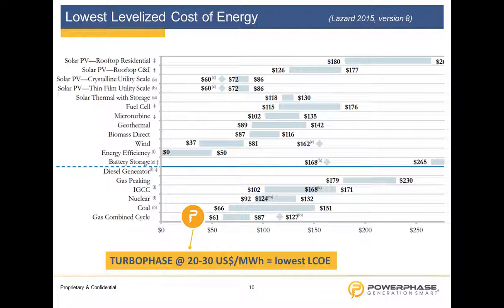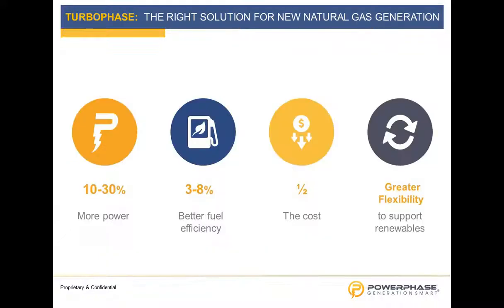I think one of the questions that popped up a little earlier while I was speaking was about how much power is consumed by the module. We're producing 6 to 8 megawatts of power on the gas turbine. We're consuming 35 kilowatts. So to repeat that, 6 to 8 megawatts on the gas turbine per module, we're only consuming 35 kilowatts of electrical power. And in that, it makes for a very flexible, easy install.